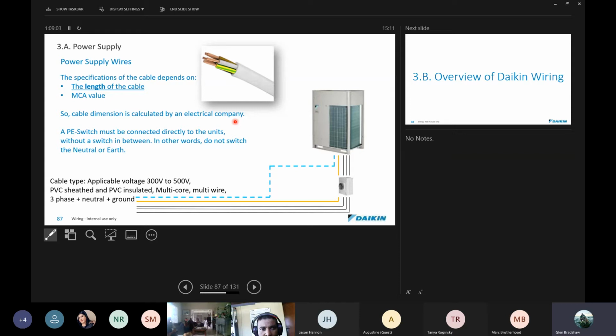And the PE switch must be connected directly to the units without switching in between. In other words, you're not allowed to switch the neutral and earth on a unit. So you only switch the three phases, the three lines, but you do not switch the neutral and earth at any time.